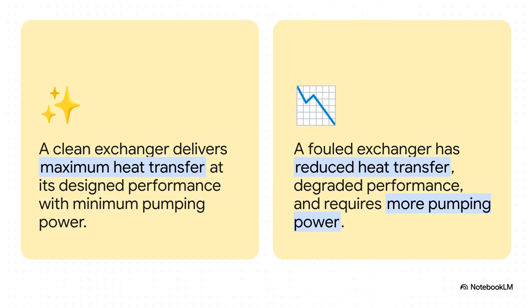And the impact is dramatic. A clean exchanger is humming along at peak performance. But as fouling builds up, it acts like a layer of insulation, choking off the heat transfer. To make up for it, you have to pump your fluids harder, which costs way more energy, all while your performance just keeps getting worse.